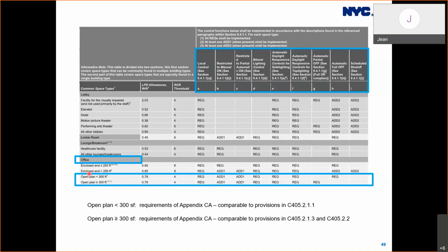So for offices, open plan, less than 300 square feet or 300 square feet or larger, their requirements here in ASHRAE are almost identical to the ECC requirements. Just note the difference between the two different size open plan areas.